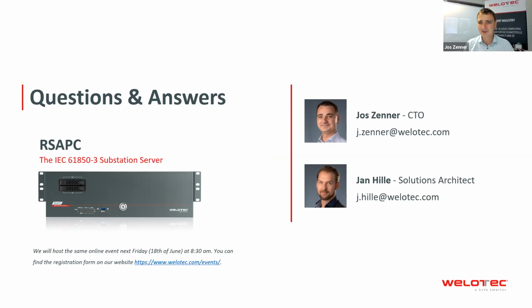So we have three different power options. They're hot swappable, so I can replace them during operation, and we have redundant power supplies. You can imagine that you have some kind of brick on the back that you can just pull out and replace with another one. And there are two of those, and in case one fails or one is replaced, the other one takes over and the system is fully operational.